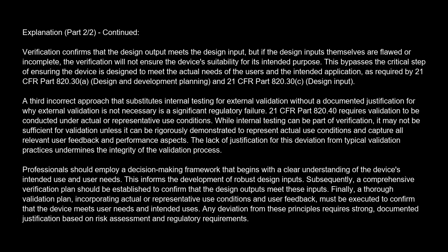Professionals should employ a decision-making framework that begins with a clear understanding of the device's intended use and user needs. This informs the development of robust design inputs. Subsequently, a comprehensive verification plan should be established to confirm that the design outputs meet these inputs. Finally, a thorough validation plan, incorporating actual or representative use conditions and user feedback, must be executed to confirm that the device meets user needs and intended uses. Any deviation from these principles requires strong, documented justification based on risk assessment and regulatory requirements.